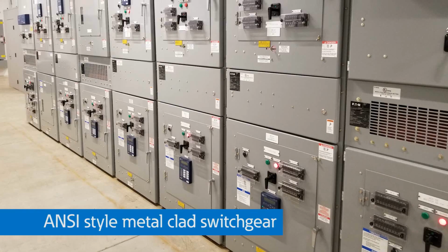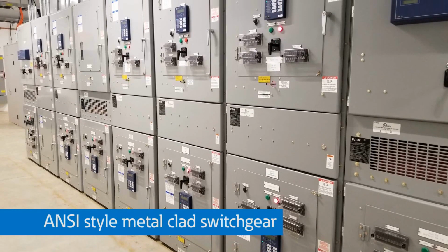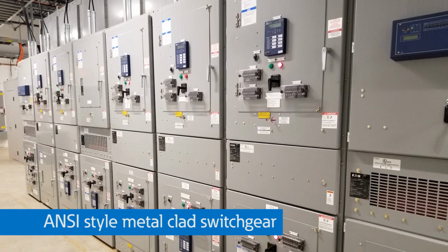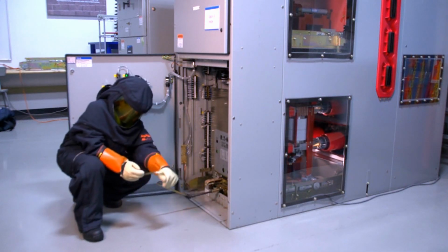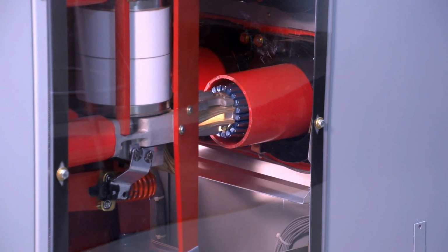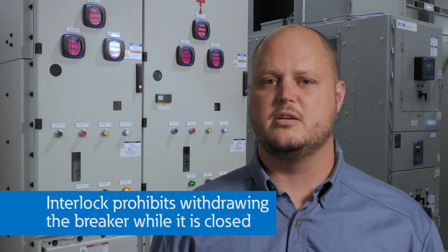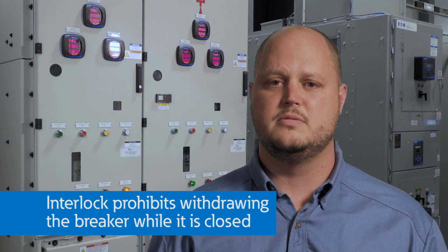Many of us are already very familiar with the ANSI style metal-clad switchgear. For metal-clad switchgear, an operator must open the circuit breaker before withdrawing the breaker to the test or disconnect positions. The switchgear is interlocked such that the breaker cannot be withdrawn while it is closed. Gas-insulated switchgear comes equipped with similar interlocking features.